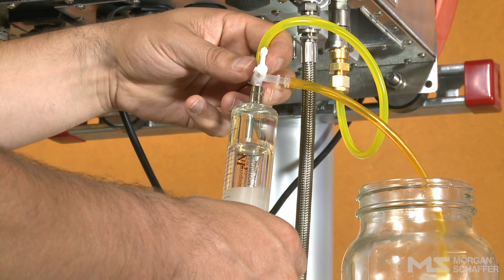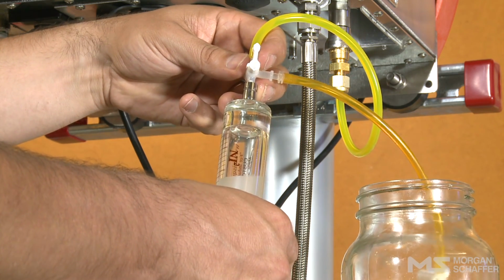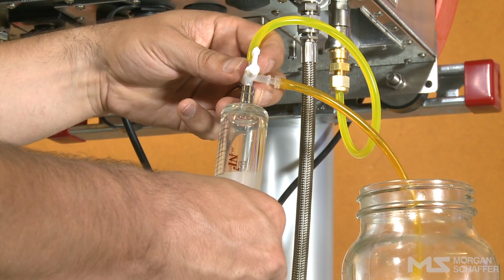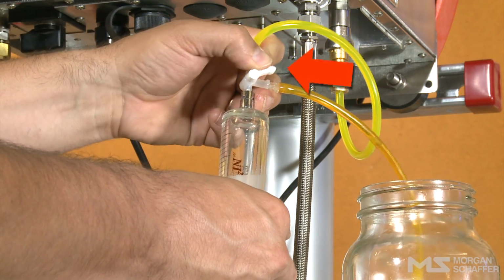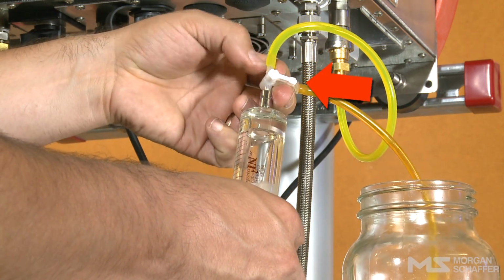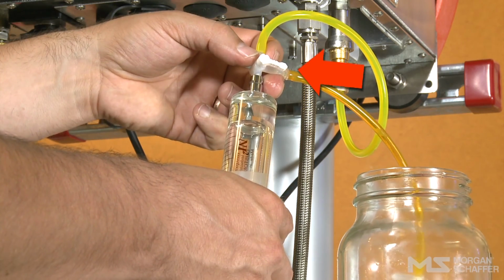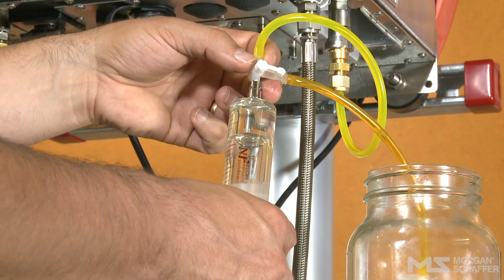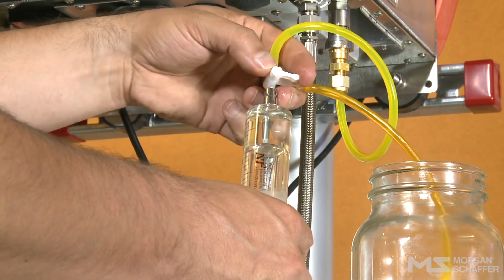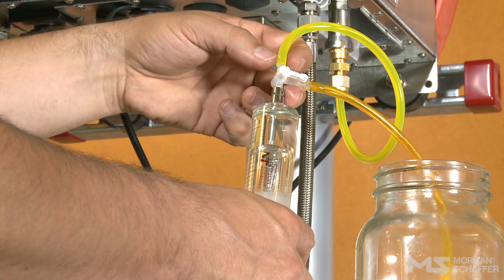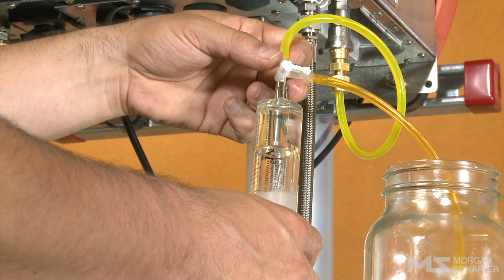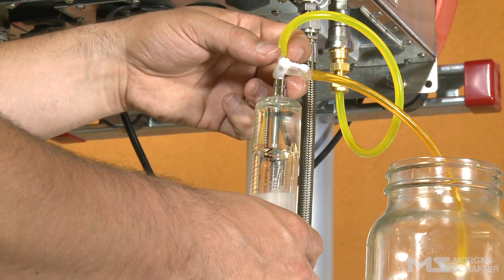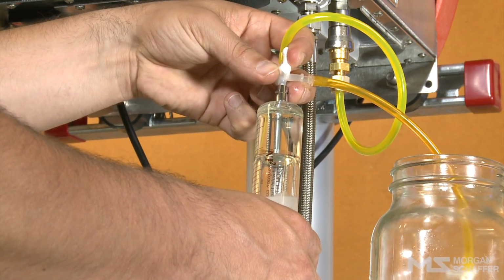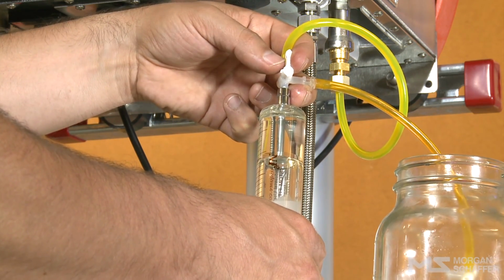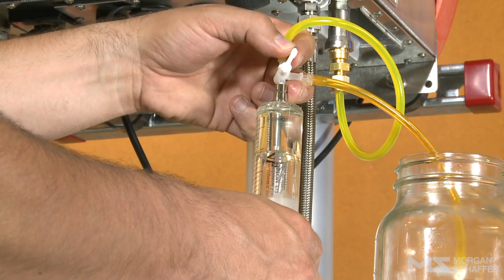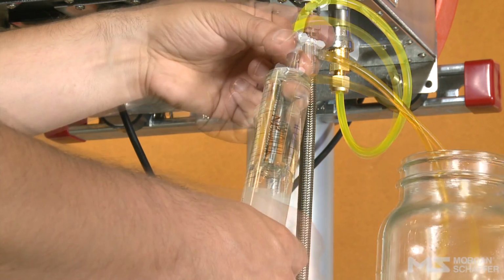This step is necessary to remove stagnant oil from the sampling valve assembly. Turn the 3-way stopcock handle toward the side port and allow the syringe to be filled with the desired quantity of oil. Do not pull on the piston to fill the syringe. Repeat the last 2 steps to ensure that there are no bubbles in the sample.